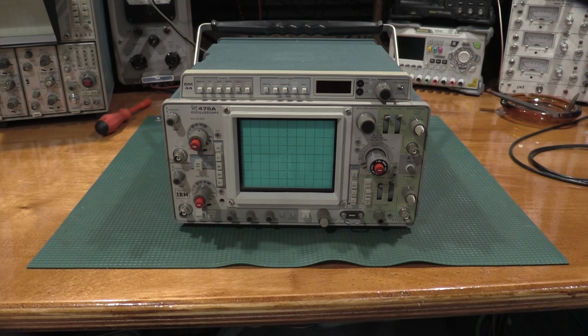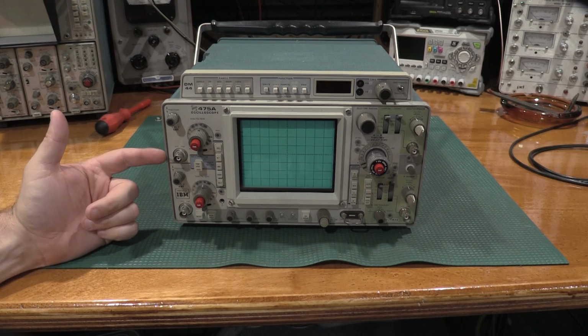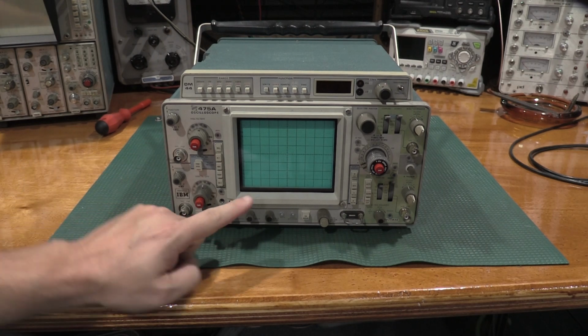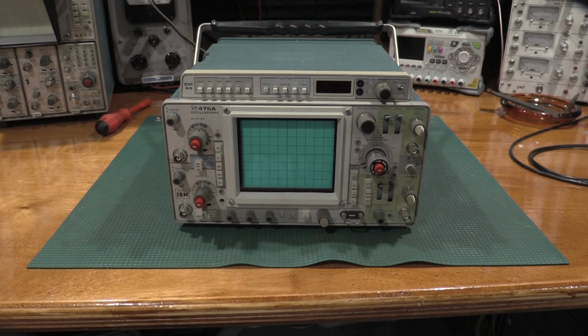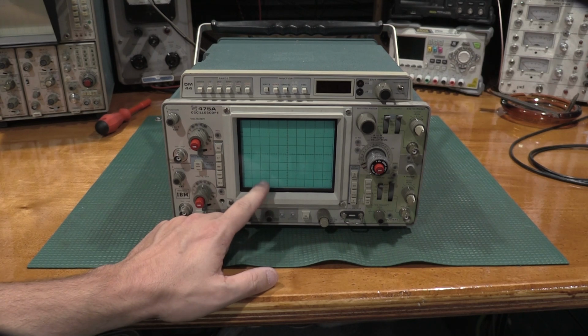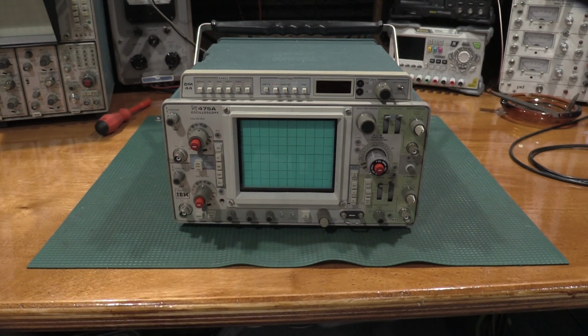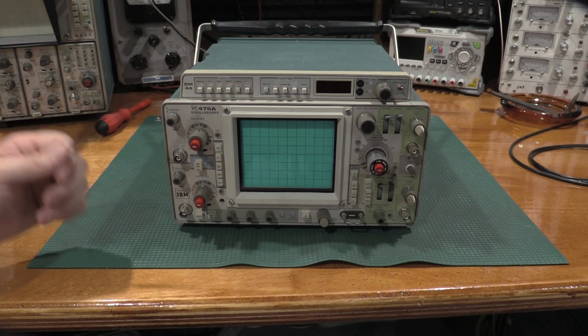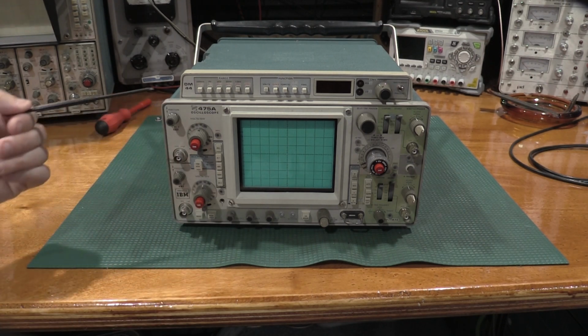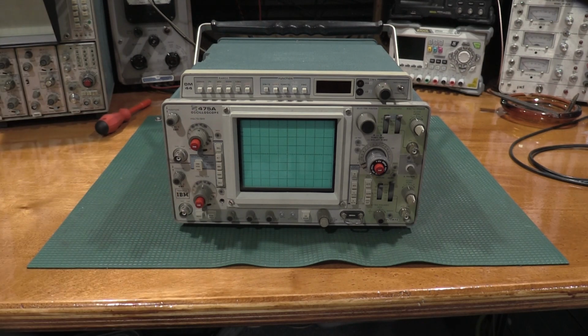But that does affect, I believe it sits after the vertical amplifier, but before the actual drive amplifier for the tube. Because the drive amplifier for the tube is, if I remember correctly, like 200 volts to the plates of the tube to get the horizontal and vertical deflection drive. We know the attenuators are toast. Being that it's a 475, we know we have transistors that we're going to have to replace.